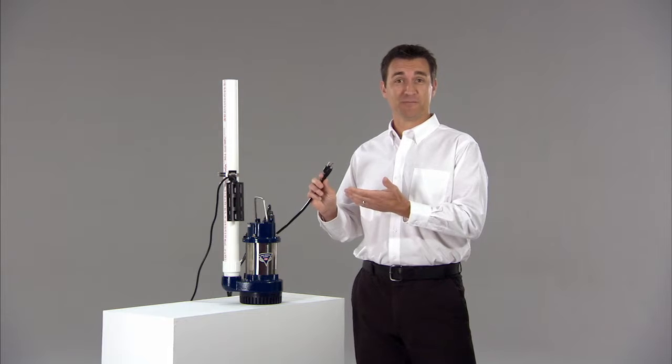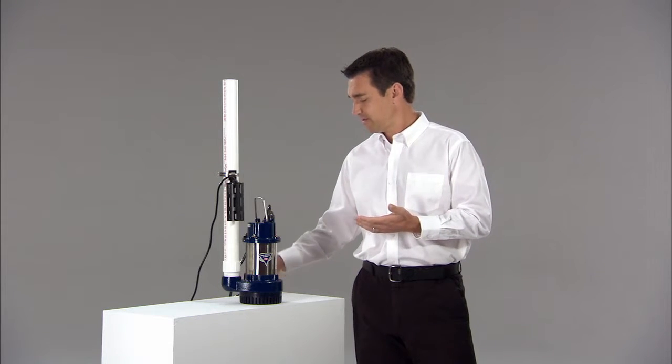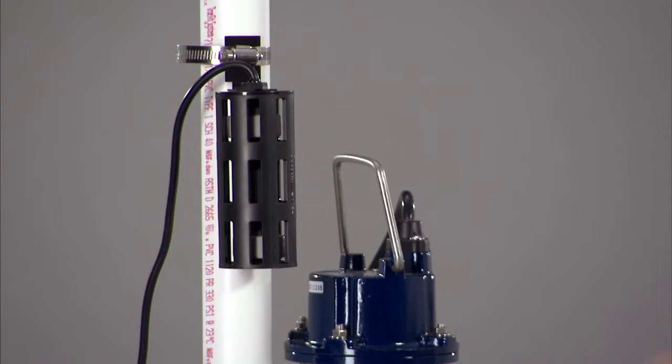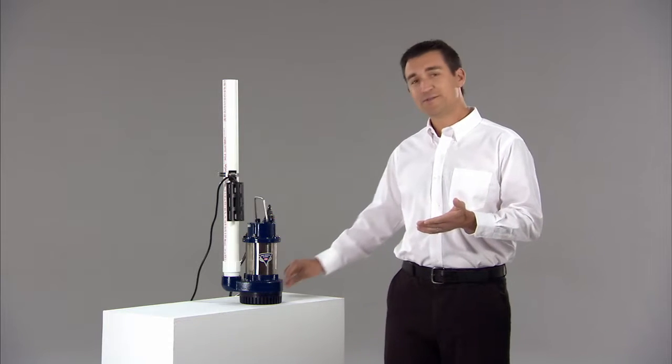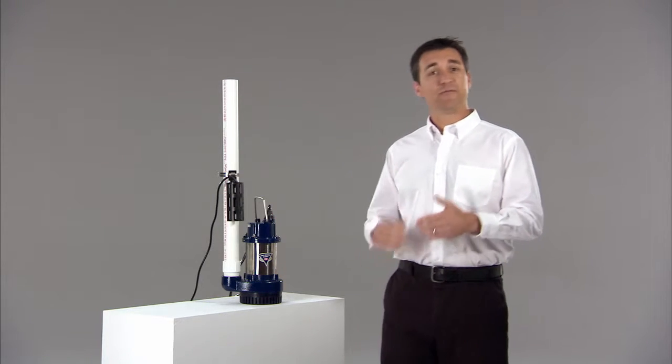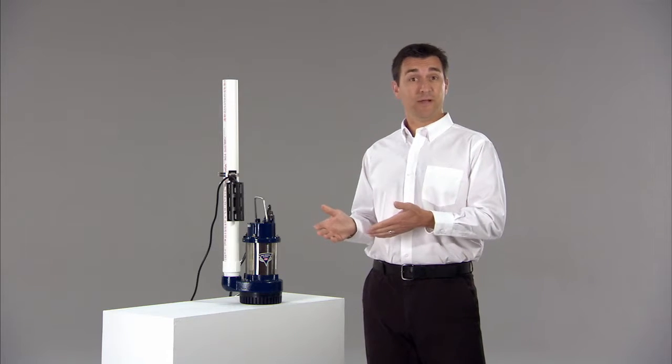First, ensure your sump pump is plugged in. Now test your pump by lifting the float. If the pump comes on, chances are you'll be okay. If there's water in the basket, it should empty. If the motor doesn't come on, you may have a problem and a wet basement.